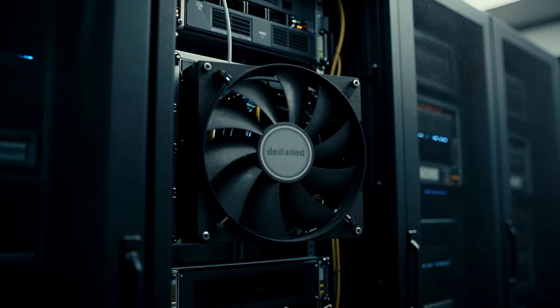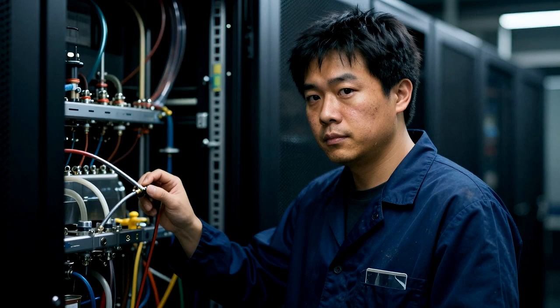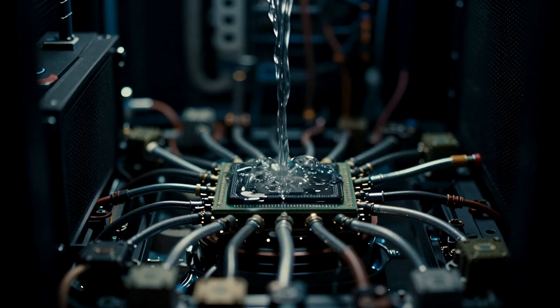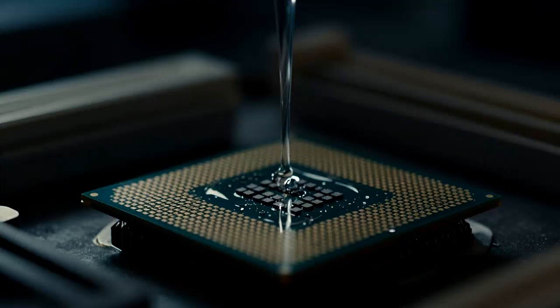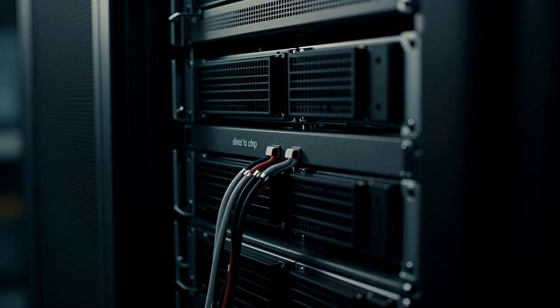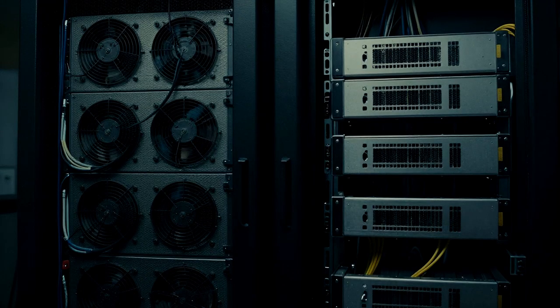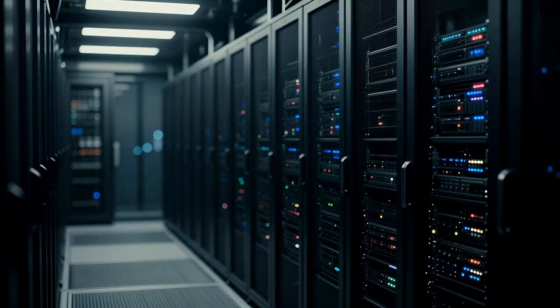With traditional air cooling thoroughly defeated by 132 kilowatt server racks, the technology industry has effectively turned to the plumber for salvation. To cool modern architecture, water must bypass the air entirely and be brought directly to the source of the fire. Direct-to-chip liquid cooling, also widely known as cold plate cooling, is currently the dominant transitional technology bridging the gap between legacy air environments and the liquid future.